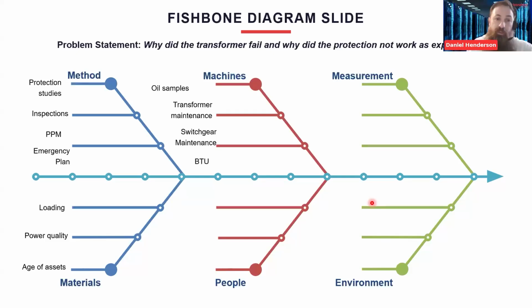Yeah, really good point. We'll cover it, but the transformer was maintained, I think, the year before. Same with the switchgear maintenance. It was done around the same time to take off that circuit, so they did the circuit breaker first. As part of that, the switchgear, they did the electromechanical relay, making sure that it was trip time tested to the setting. Like I said, we covered the oil samples and the transformer maintenance. You'd done what you could. Everything seemed to be fine. The battery tripping unit was done at a similar time, not in that same period, but at a similar time. It was an older type unit, but still fairly reliable. Anything from you, Johnny?